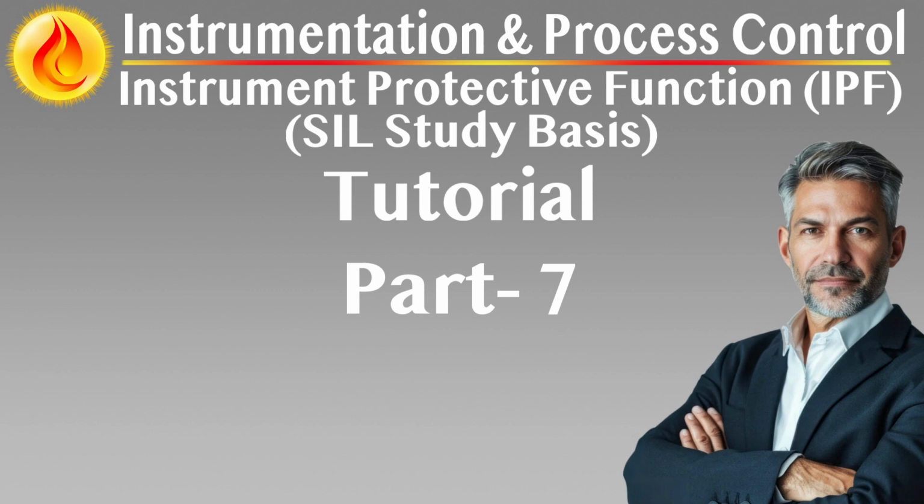Alarm management and operator interface. Clear alarm prioritization. Fire and gas alarms must be clearly distinguished from process alarms and given top priority on operator interfaces. Alarm messages should identify detector location, type of hazard, and time of activation.